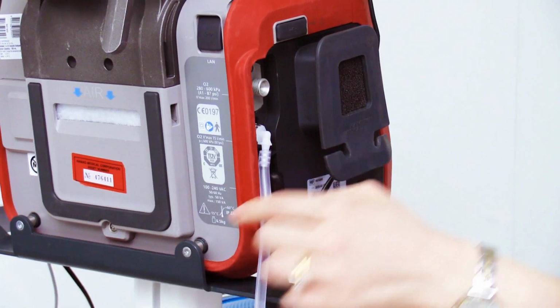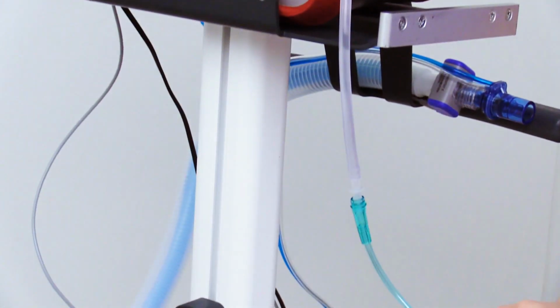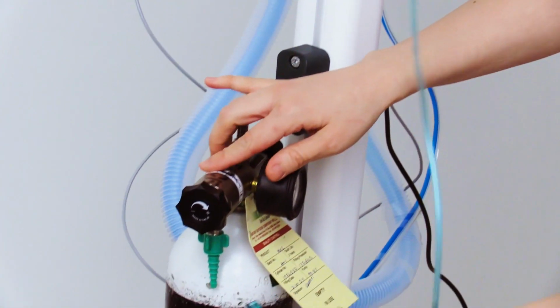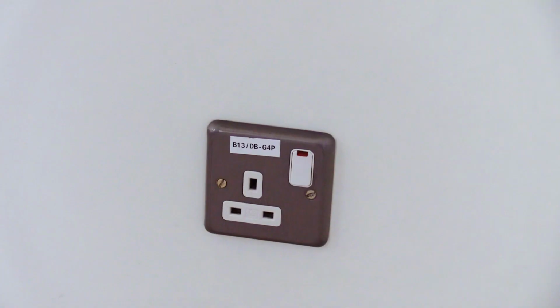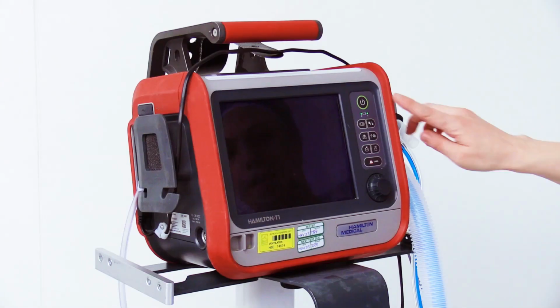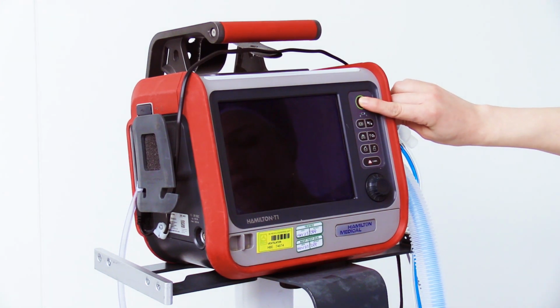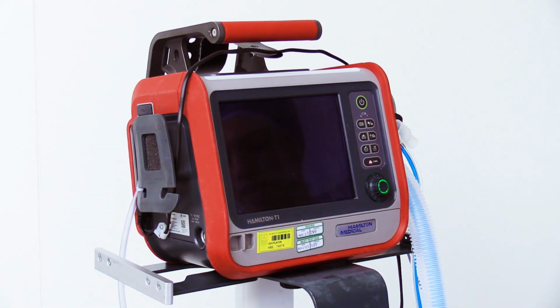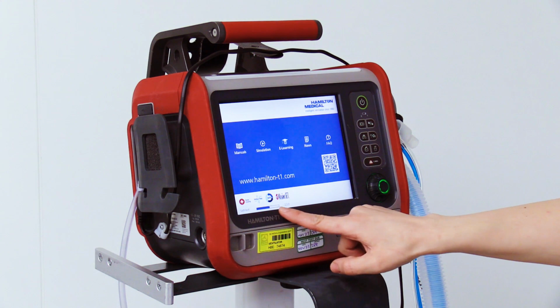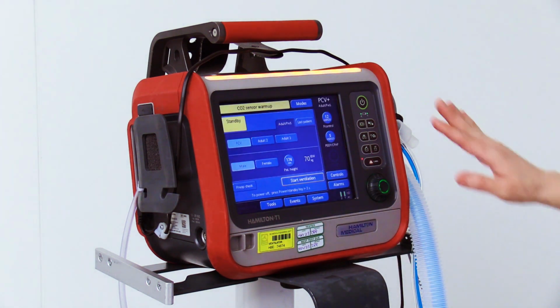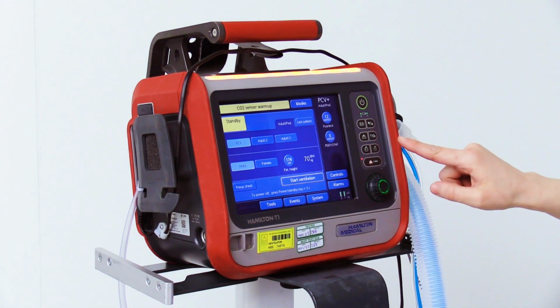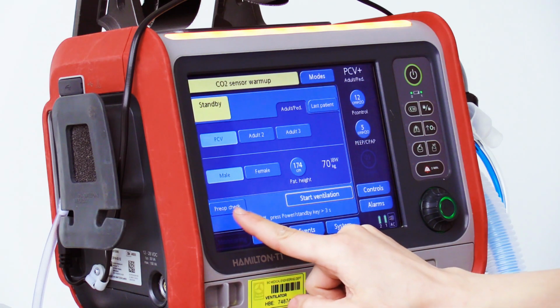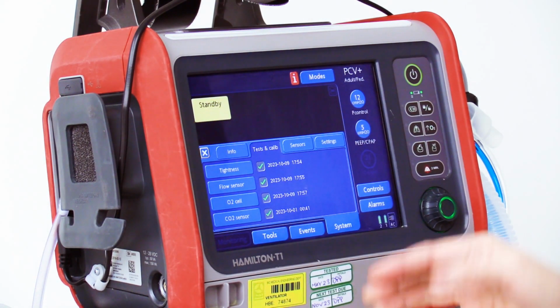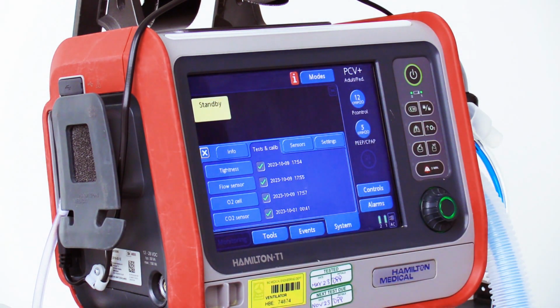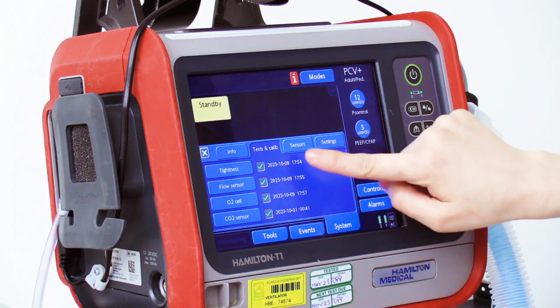Pre-op checks. Before starting pre-op checks, make sure that the ventilator is connected to both oxygen supply and power supply. Press the power button to turn on the ventilator. The ventilator will automatically run a self-test. Once that's finished, you can go ahead and touch the pre-op checks here. And here in this window, you can access the tests and calibration functions.